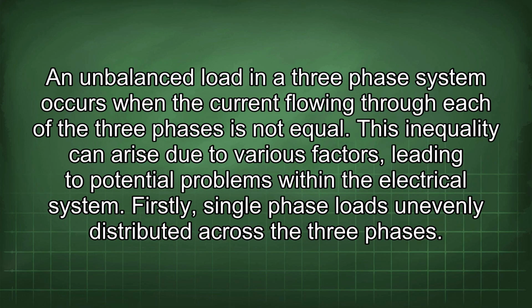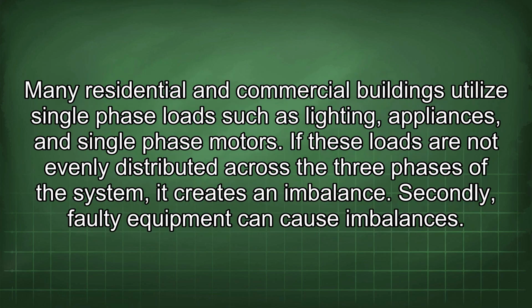An unbalanced load in a three-phase system occurs when the current flowing through each of the three phases is not equal. This inequality can arise due to various factors, leading to potential problems within the electrical system. Firstly, single-phase loads unevenly distributed across the three phases. Many residential and commercial buildings utilize single-phase loads such as lighting, appliances, and single-phase motors. If these loads are not evenly distributed across the three phases of the system, it creates an imbalance.